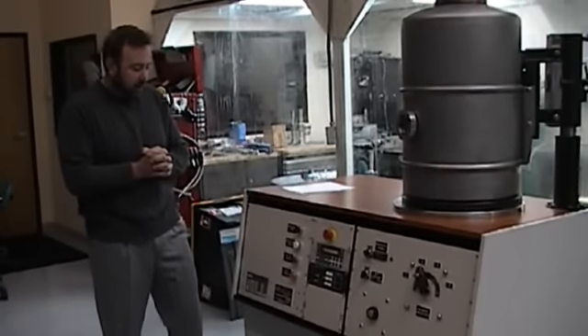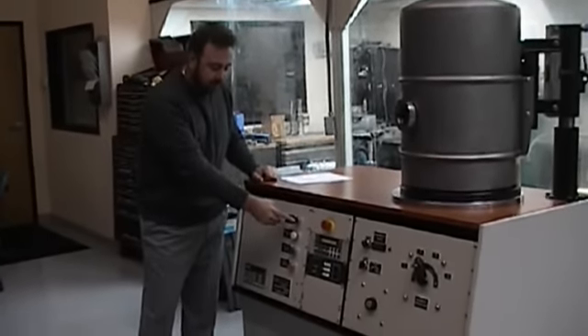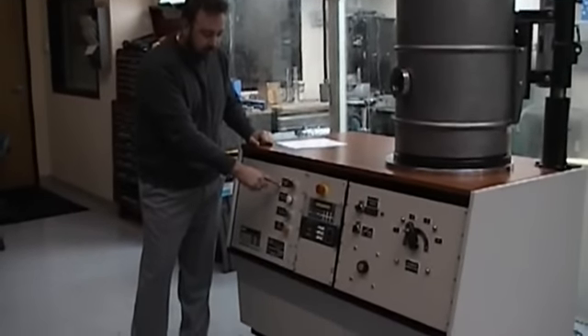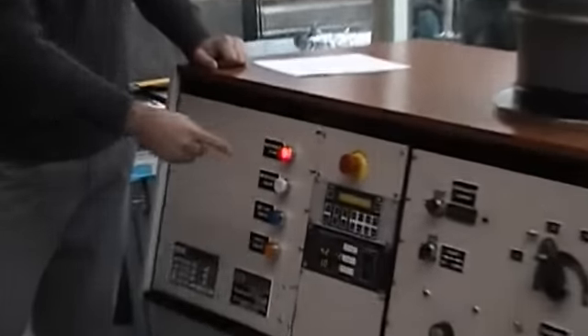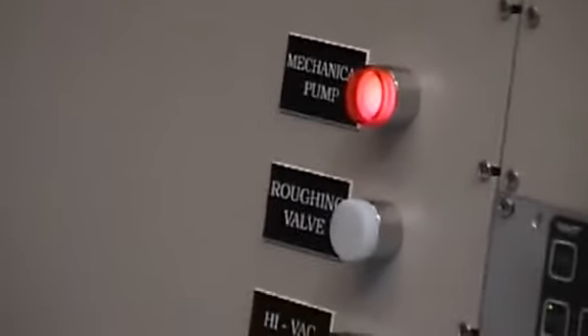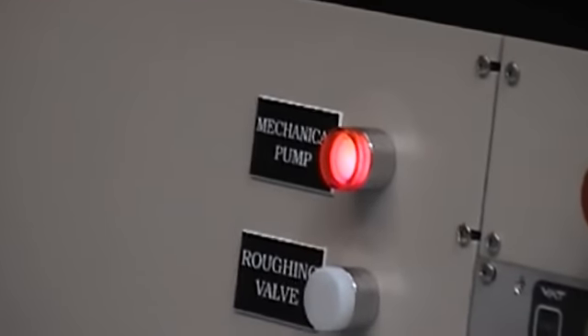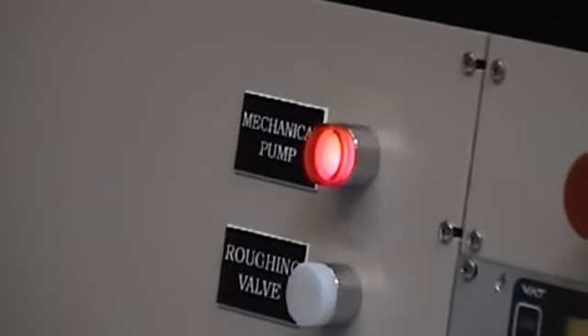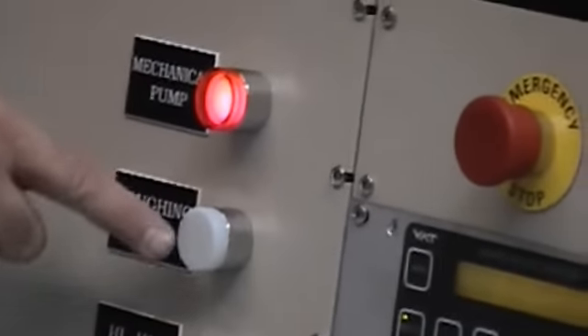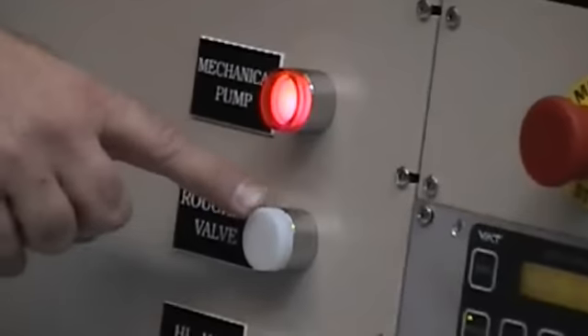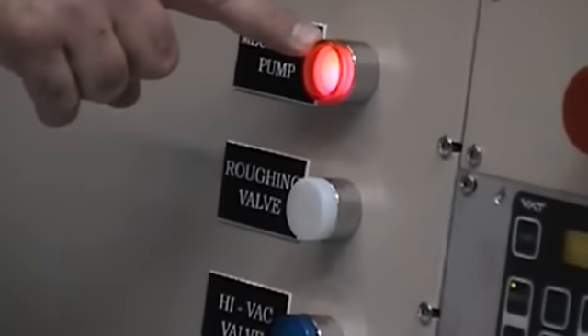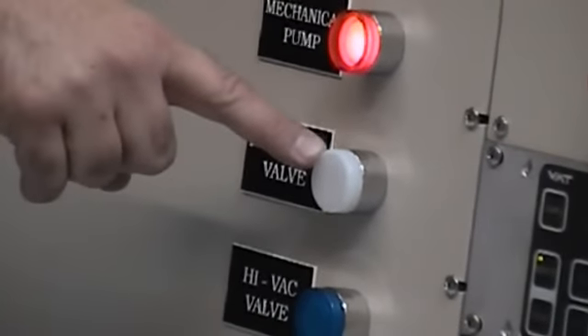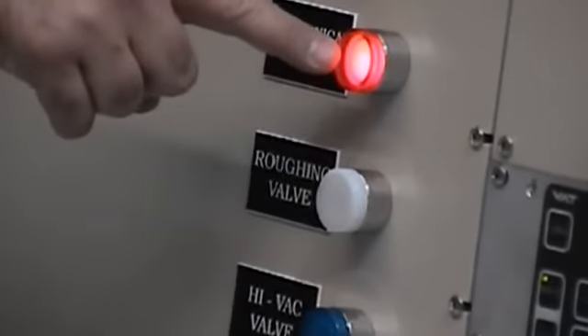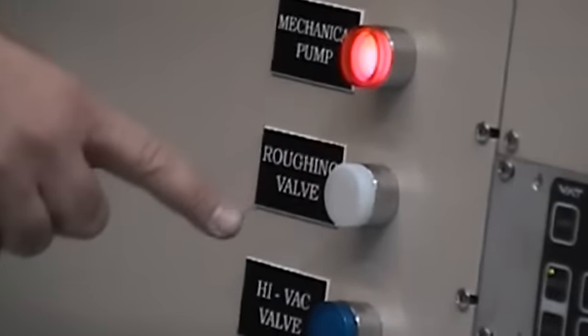First off, I'm going to go ahead and operate the mechanical pump. The mechanical pump is located up top. As you see, when you depress the switches, the pilot light will come on. The roughing valve is interlocked with the mechanical pump, so the roughing valve cannot open unless the mechanical pump is on.